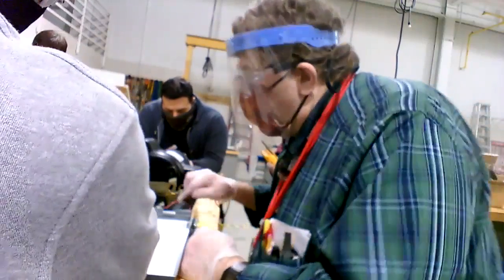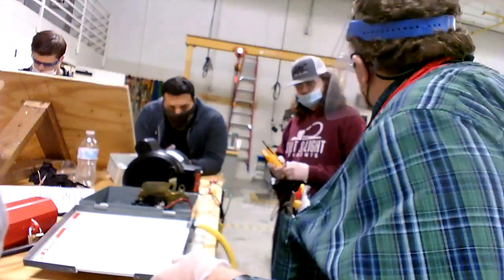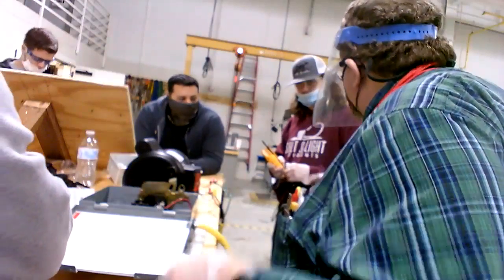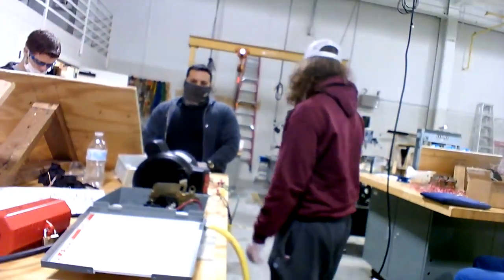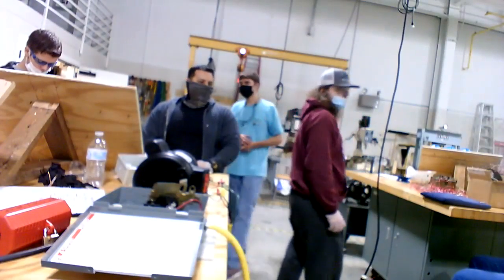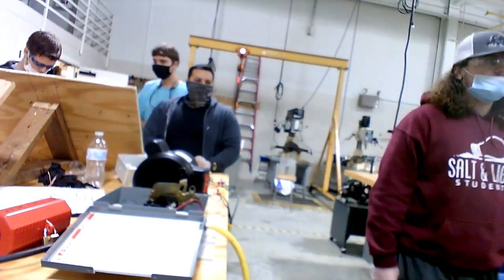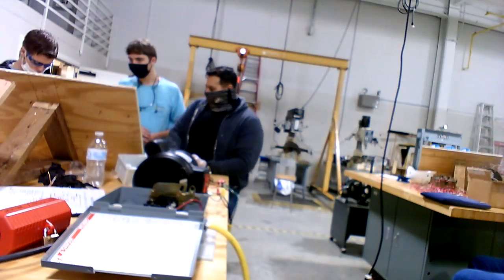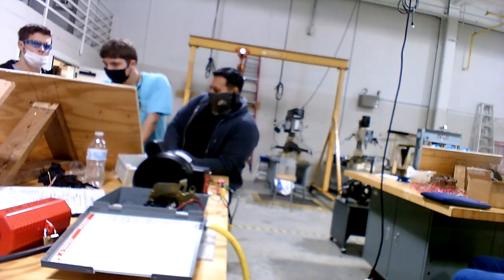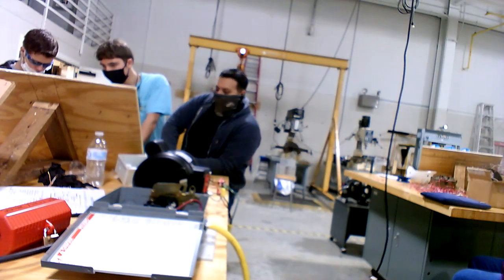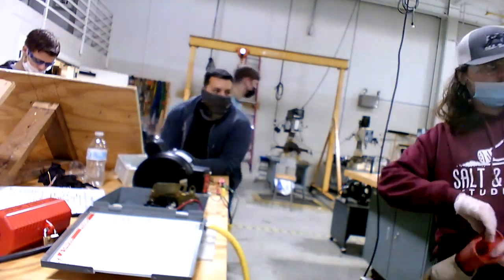Okay, the plan is hooked up, so that's good. And so you've got your shield application? You're going to need the jacket on, electric gloves. Yeah. I think the arc flash shield is over there. You got the shield over there? Yeah. Good, put your gloves on. If you're over 50 volts, you got to have them on.